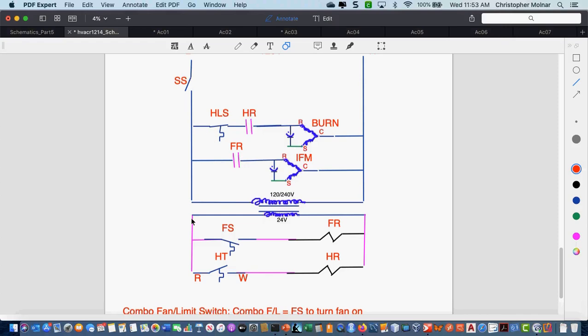I see a lot of guys wiring the limit switches down. I'm just going to point to it with arrows because I don't want to confuse everybody. I see a lot of guys putting the limit switches right here. What's wrong with putting your limit switch right there? You'll cut power to FR and HR. Well, I don't mind it cutting power to HR. Power is just being fed to it. There's no safety from the transformer. Yeah. Well, basically, if I put my limit switch right here, if that limit switch opens, I'm cutting out my fan relay, and I'm cutting out my thermostat.